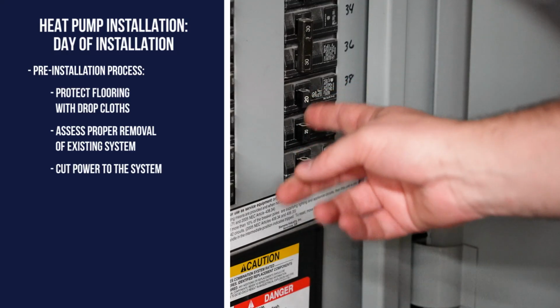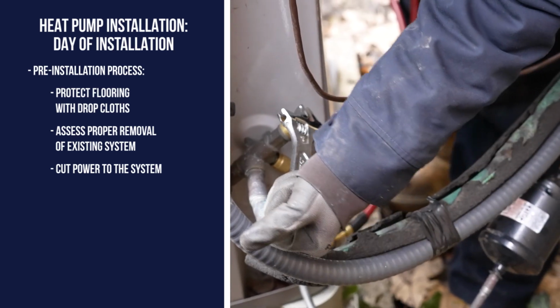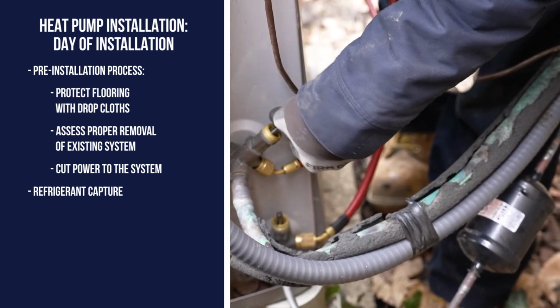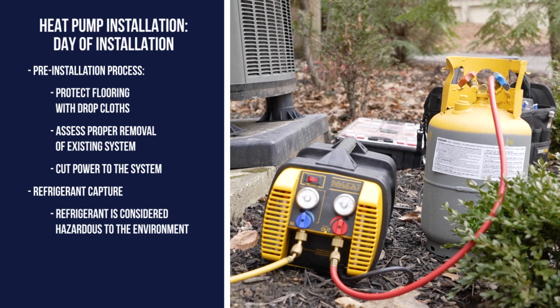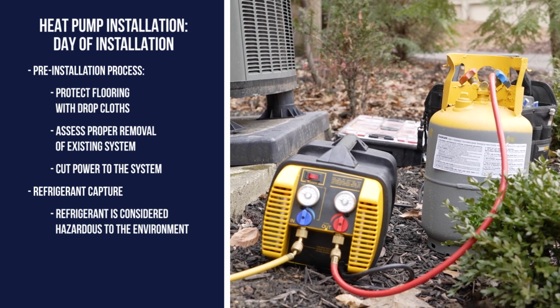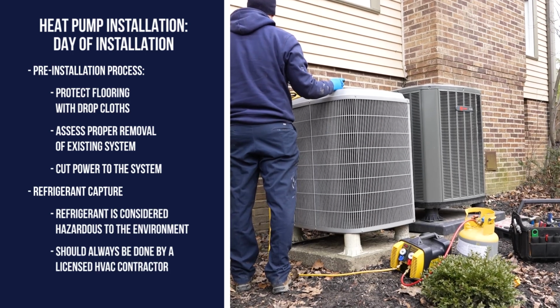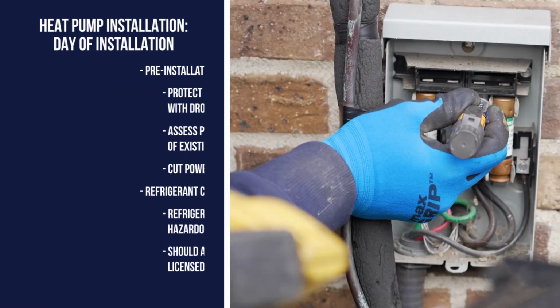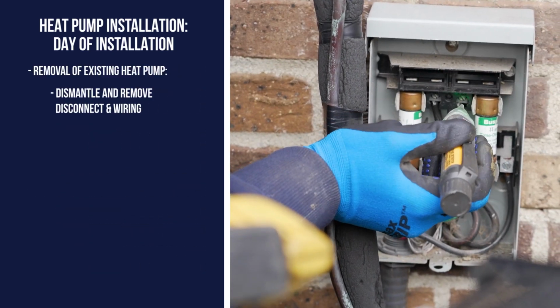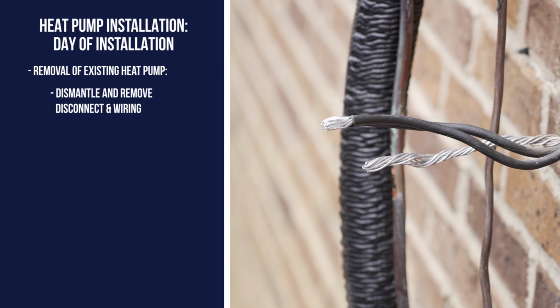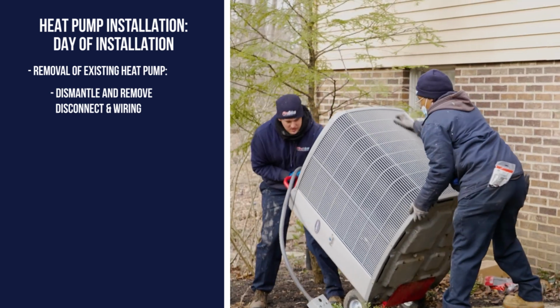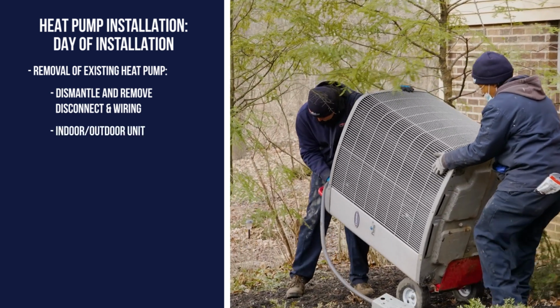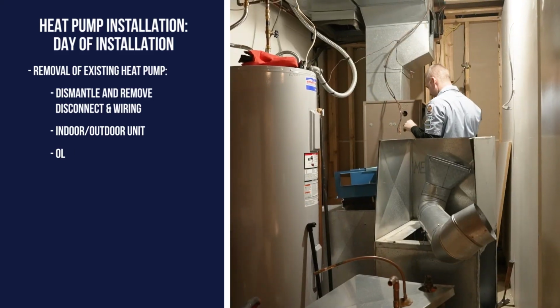With the plan in place and power cut off to the heat pump, the installers will begin by capturing the refrigerant inside the heat pump. Refrigerants are considered hazardous to the environment by the EPA, and licensed contractors should take this step. While the refrigerant is being captured, the disconnect is dismantled and removed, as well as the wiring to the heat pump.